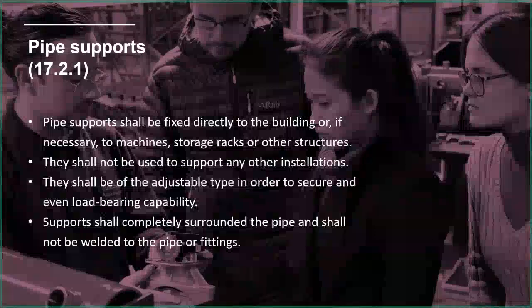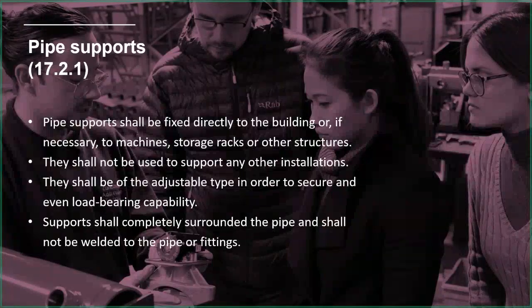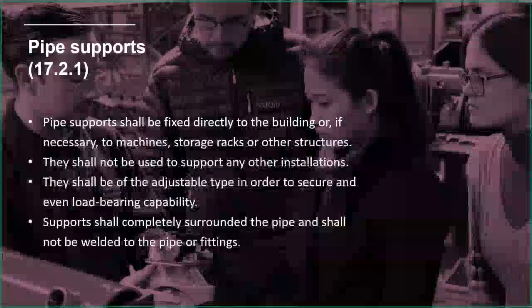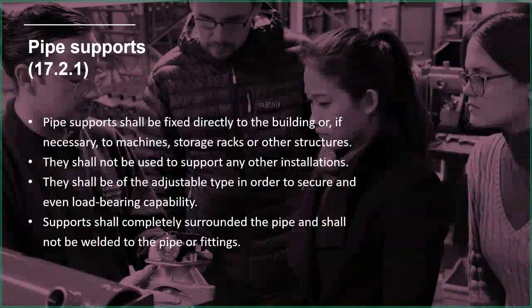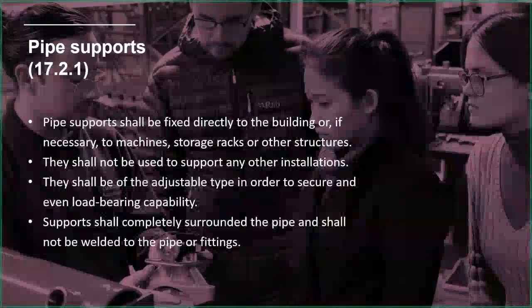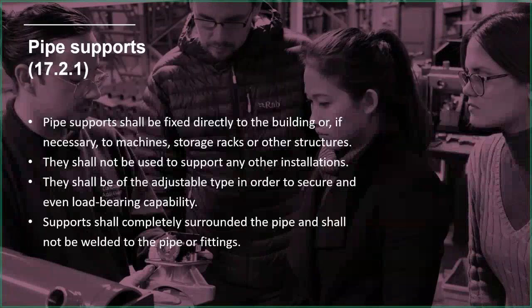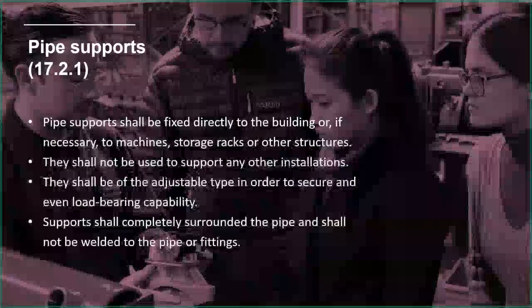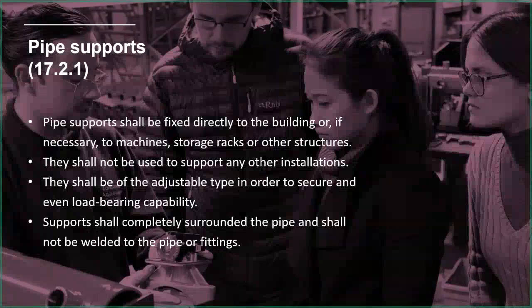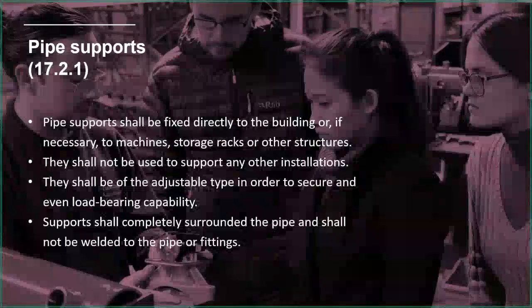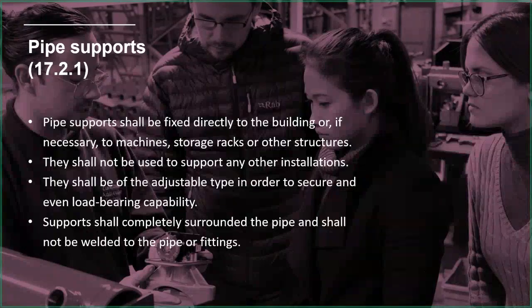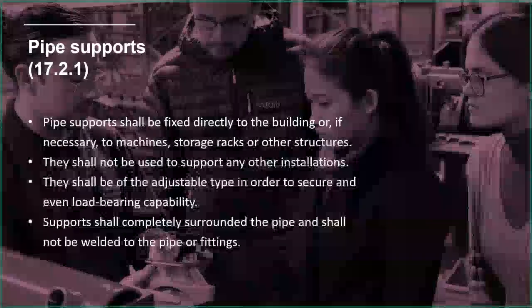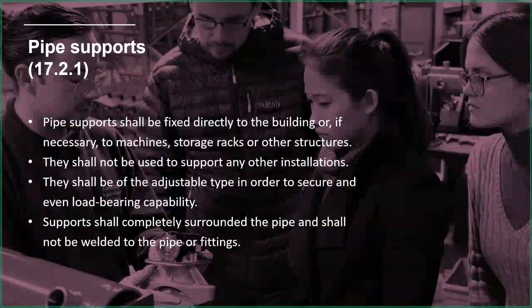I guess it's quite rare to do that, and obviously it should be avoided where possible. Supports should not be used to support any other installation. It's quite common that other services will kind of steal support from other people - I've seen that where you've got a pipe hanger with sprinkler pipe, and then underneath a cable tray supported off the sprinkler pipe, which is supported off the ceiling. The point is that everything is calculated as far as load-bearing strength is concerned, so if other services piggyback off the same support, it'll probably be fine, but it hasn't been calculated, so we don't know the total weight, and therefore it shouldn't be done.